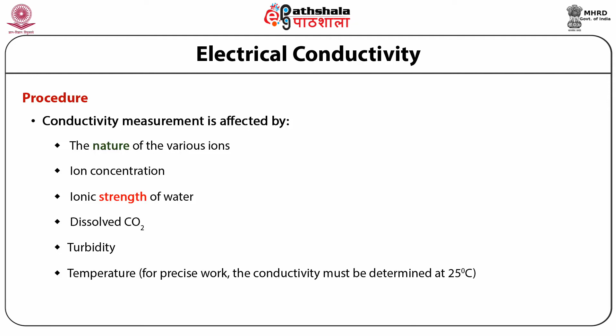For precise work, the conductivity must be determined at a temperature of 25 degrees Celsius. Most of the commercially available instruments for the determination of conductivity are made up of a source of alternating current, a Wheatstone bridge and a null detector. These instruments are based on the principle of the Wheatstone bridge, where the presence of ions creates an imbalance in the arms of the bridge, which is detected as a current. This deflection in current is directly proportional to the concentration of ions present in the water.